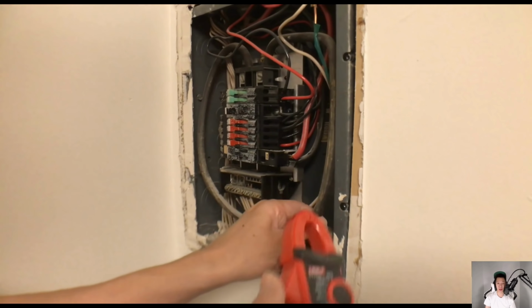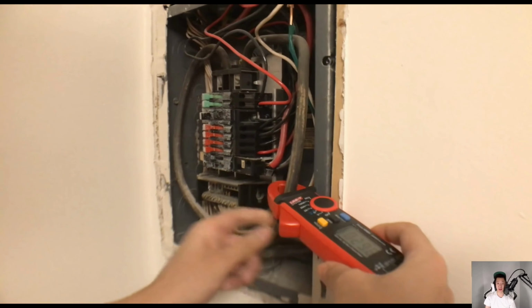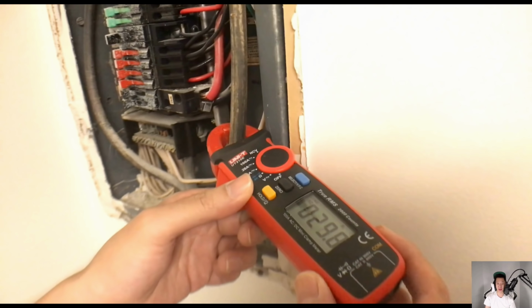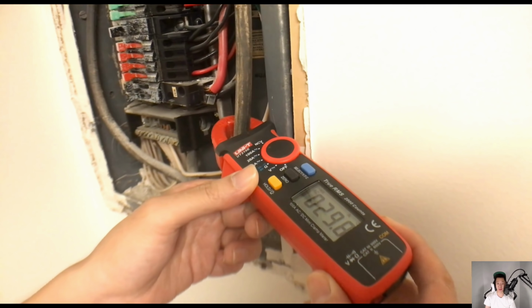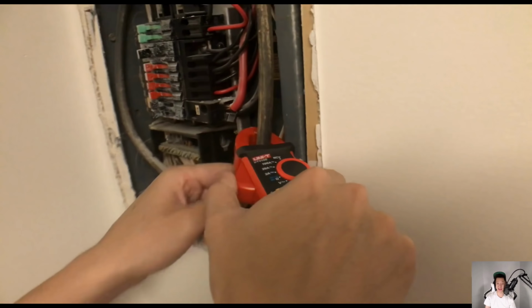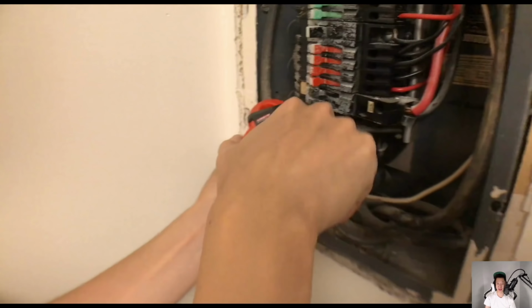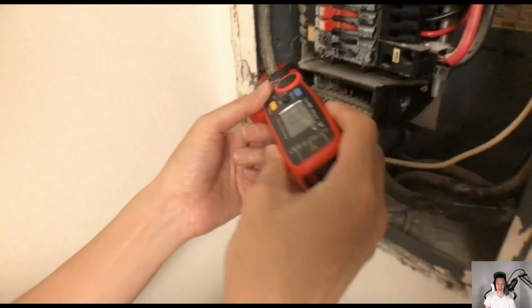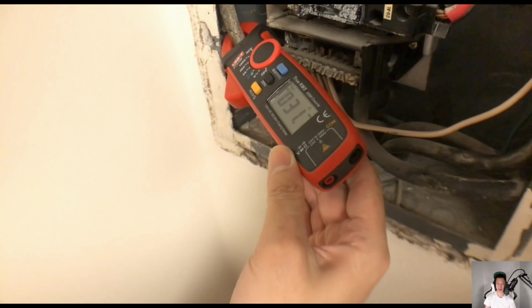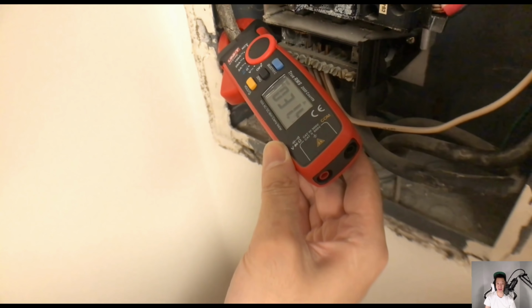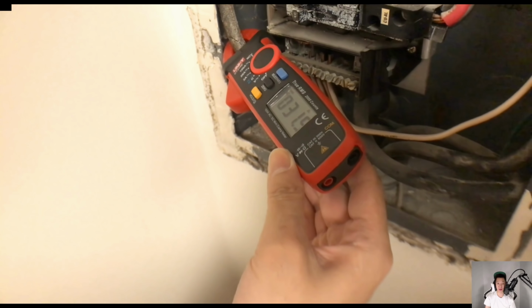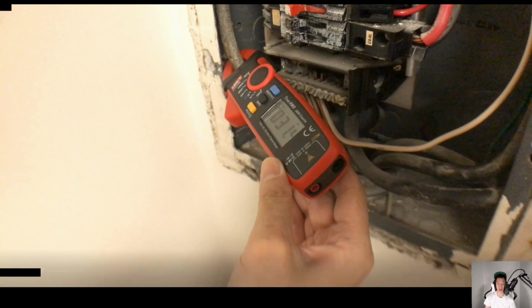Okay, so to measure the power, I am going to use this clamp meter. Now, as you can see on this first main wire, I am using about 29.5 to 29.6 amps. And on this next main wire, I am using about 31.5 to 31.7 amps. Now that is way below 80% of 50 amps.